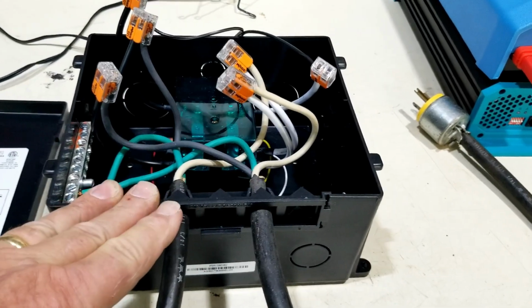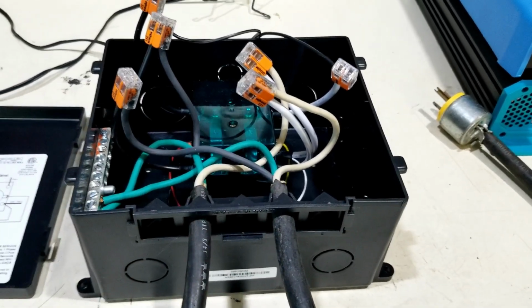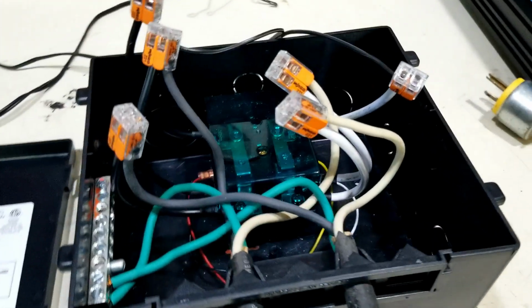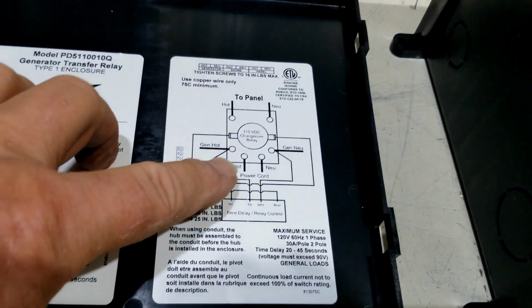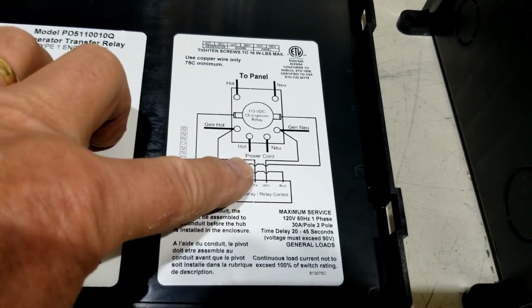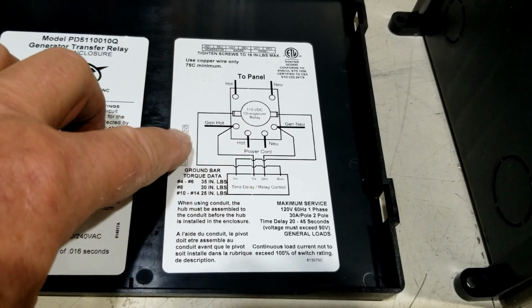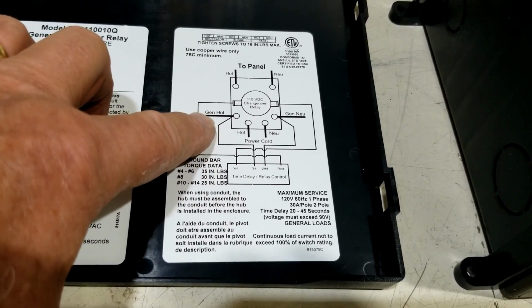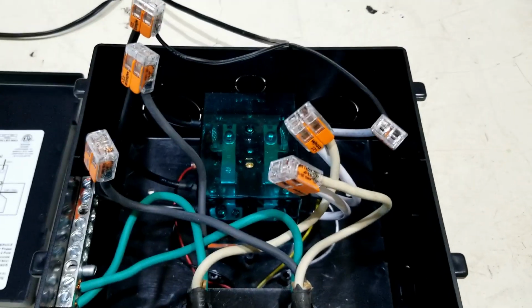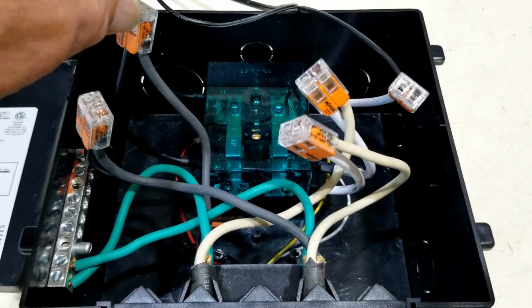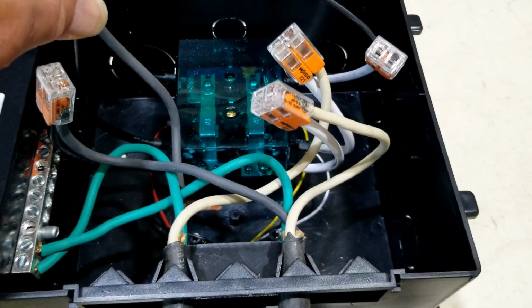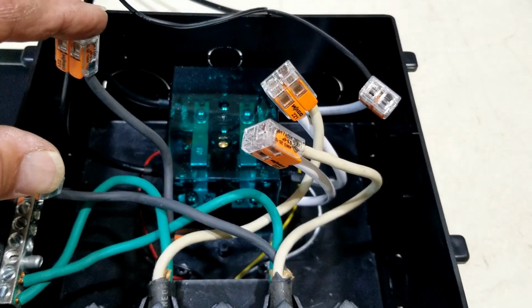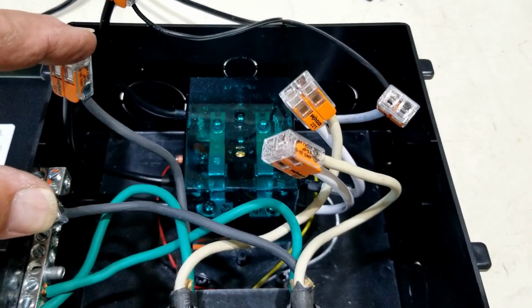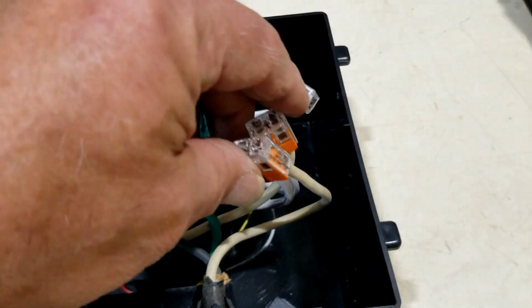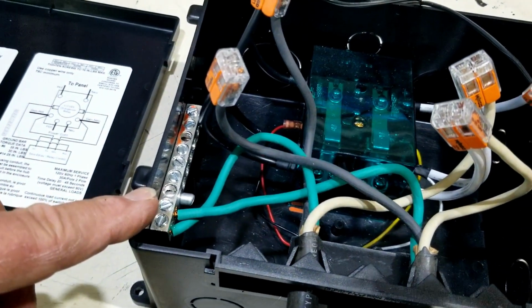Now let me walk through how this is going to actually be connected in my 303 RLS. Instead of shore power, this is going to be my inverter power, and instead of generator power, this is going to be my shore power. The automatic transfer switch effectively isolates both the positive sides, the hot sides of our circuit, and the neutral sides. The only thing that stays tied together would be your ground wires.